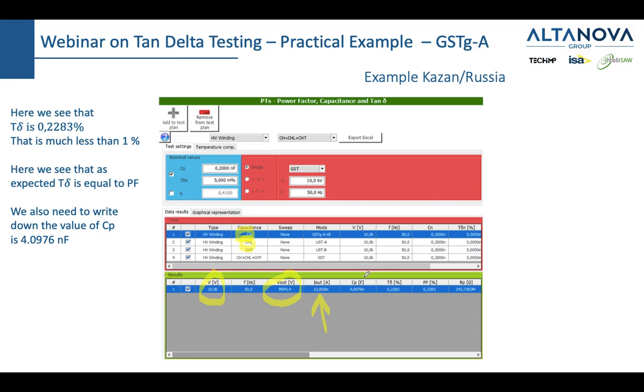And the capacitance between the high voltage and the ground was 4.0976 nanofarad. The tan delta is the number we're looking for, and we have here 0.2283, which is more than a good result since it's less than 1%. And you can see that the power factor is the same as tan delta. And that's what we mentioned before, up to 10 degrees, they're almost the same. And even up to 5 degrees, they're the same up to, I think, even the third decimal.